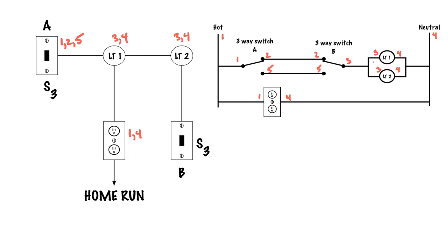Three-way switch B has got number three to the common, two to a traveler, and five to a traveler — so two, three, and five. And the last thing is the home run, which is my hot and my neutral, which is one and four.